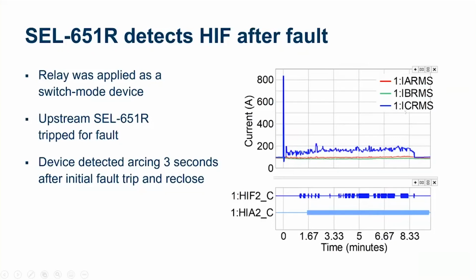But you can see enough arcing on the C phase. C phase has arcing of about 200 amps. But again, this amount of fault current is not enough for my 50 and 51 elements to pick up. So my overcurrent and time overcurrent elements cannot pick up because this is not sufficient current for them to trip on this. But as you can see, my high impedance fault bits picked up.